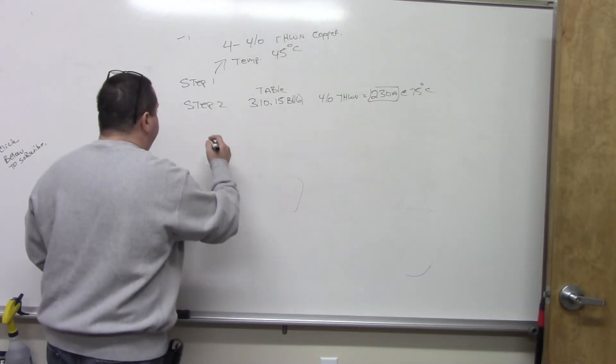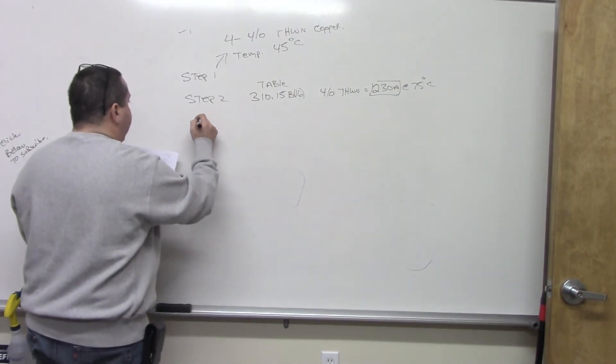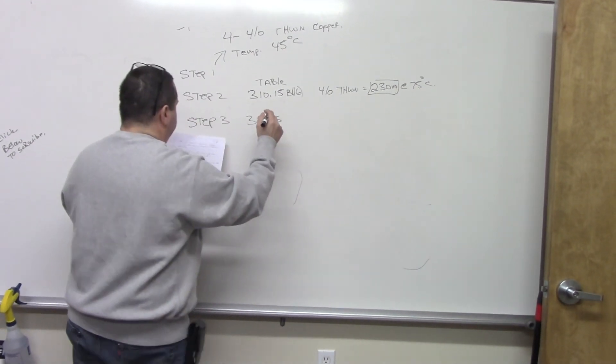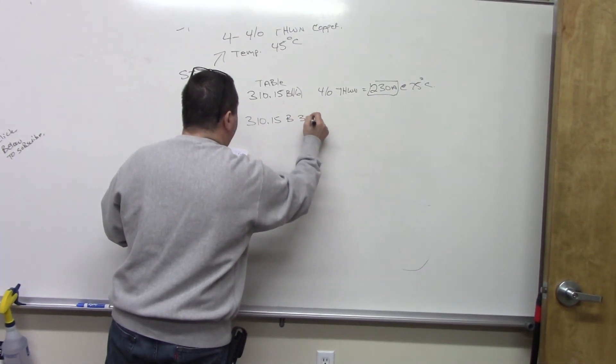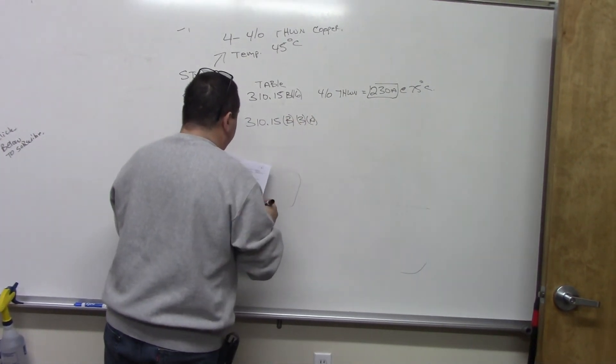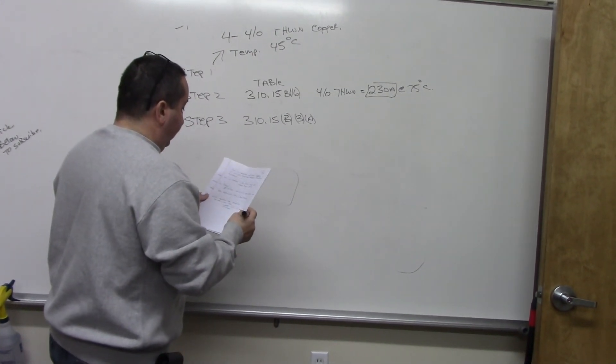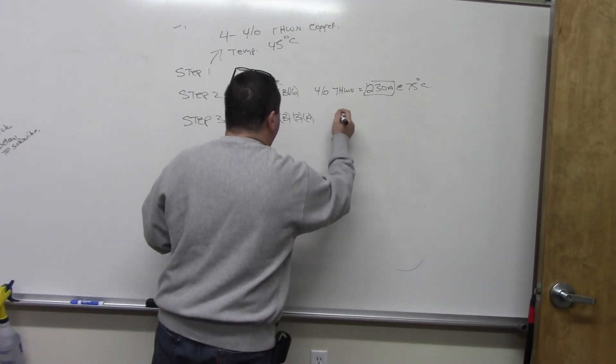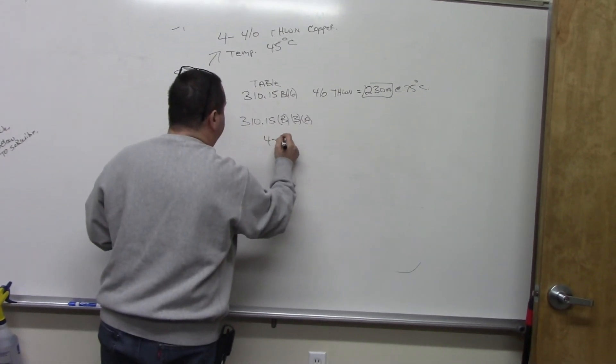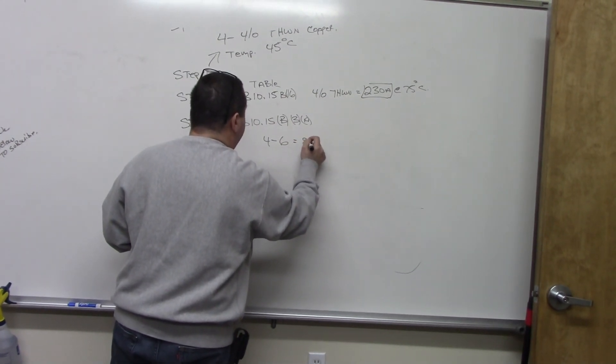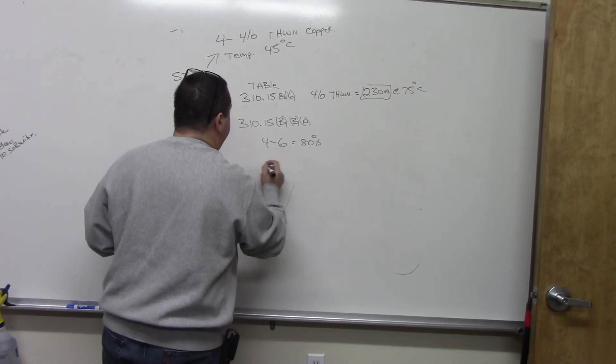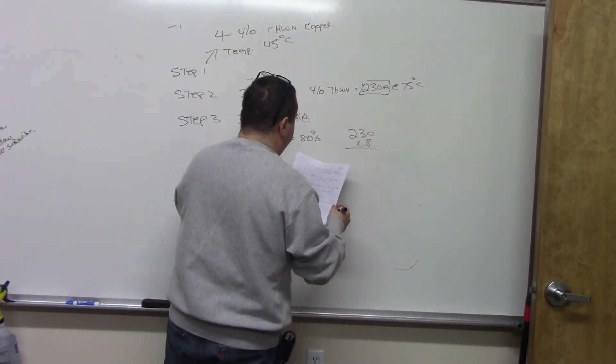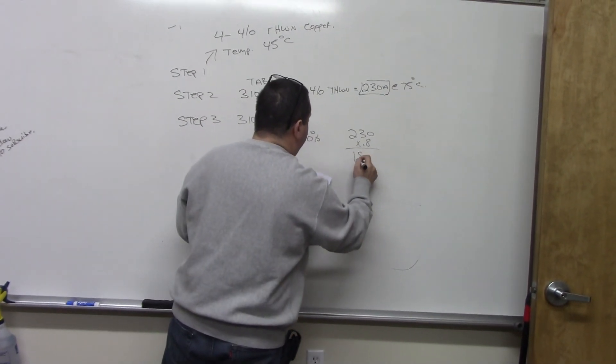For the adjustment factor, step three, we go to 310.15B3A. We look that up and find out that for four current carrying conductors, four to six is equal to 80%. So we take the 230 times 0.8, which equals 184 amps.